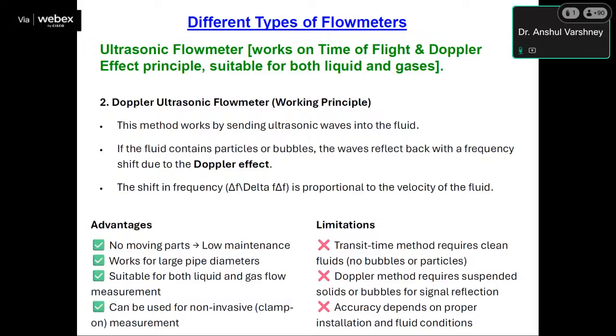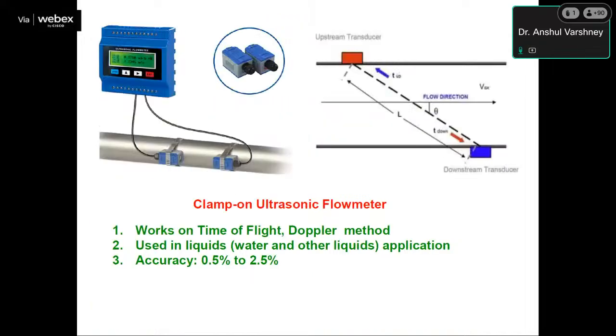The behavior of these types of flow meters mainly depends on the type of installation. You should know correctly the diameter of the pipe, the material of the pipe, the thickness of the pipe, and the type of fluid which is flowing in the pipe. Unless you know all these things, the performance of the ultrasonic flow meter will not come out as expected. This is the way we are mounting the ultrasonic flow meter.